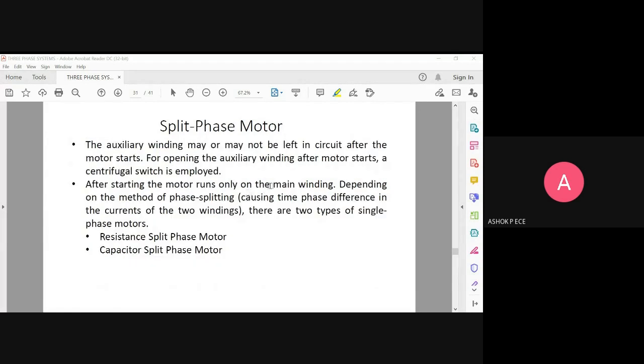The auxiliary winding may not remain in the circuit permanently. When the motor starts, the auxiliary winding will be cut off. Once cut off, the motor runs with only one winding. Depending on how the phase is split, you can have a resistance split-phase motor or a capacitor split-phase motor.